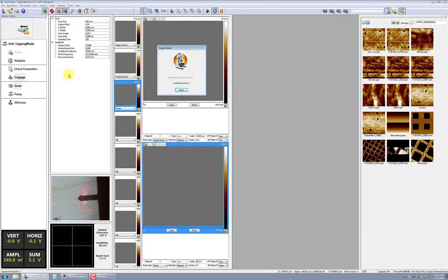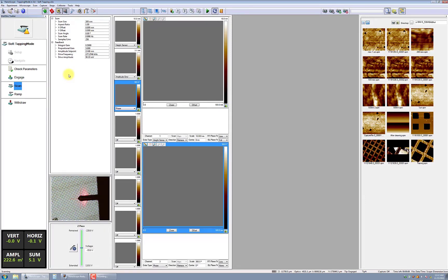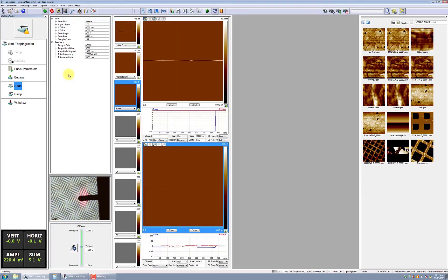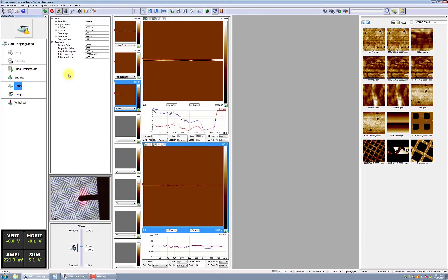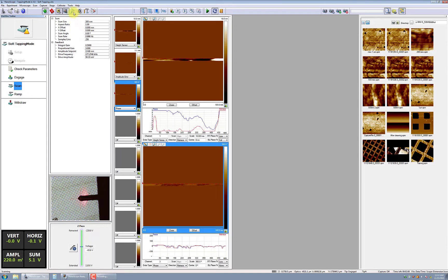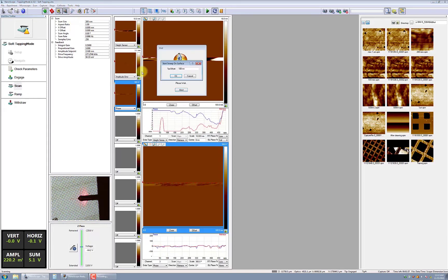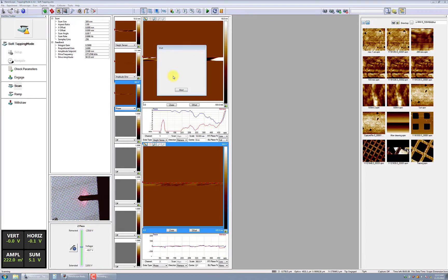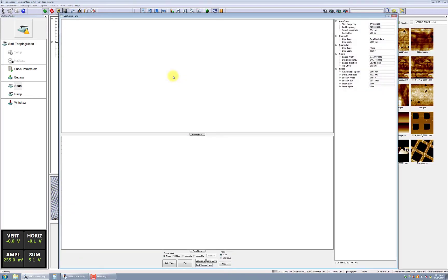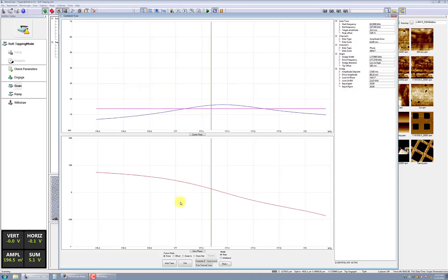Scanning will begin automatically after the beep, indicating that the tip is engaged with the sample. After engagement, click on the Tuning Fork icon located at the top of the screen to fine-tune the probe. Confirm that the offset is 100 nanometers and then click Auto-tune. Click Exit when done.